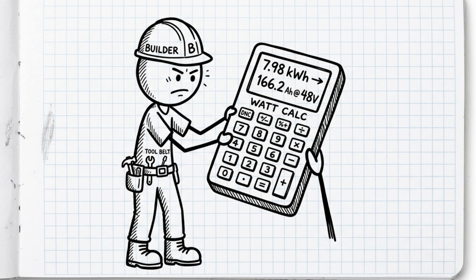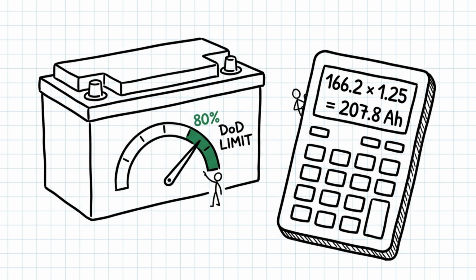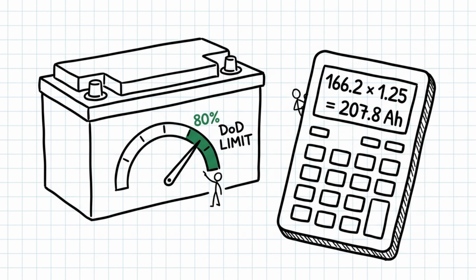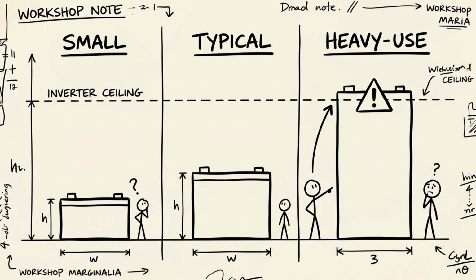Convert that to amp-hours, or Ah, on a 48-volt bank. 7.98 kilowatt-hours times 1,000 divided by 48 volts, approximately 166.2 Ah of battery has to be discharged. But you never run a battery to zero. Depth of discharge, or DOD, limits are typically 80% for lead-acid batteries, which means you need 1.25 times the raw number as your usable bank size. 166.2 Ah times 1.25, approximately 207.8 Ah minimum. That's your typical scenario. Size smaller, and you're in the small scenario, running out mid-outage. Oversize the bank without checking the inverter's continuous rating, and you've bought heavy-use battery capacity feeding through a small scenario inverter, which brings us back to the ceiling from a moment ago.